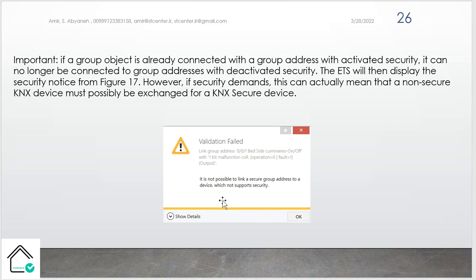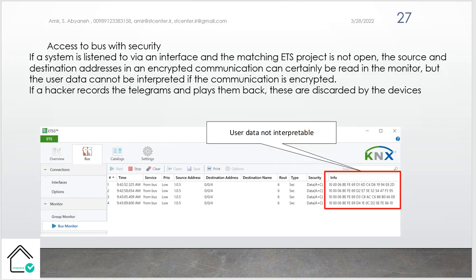If your group address is in automatic mode and you want to add a group object, it asks you, it's automatic, and if you add the non-secure group objects, it automatically turns to non-secure group addresses. But if your group address is secure and is in on mode, and you want to add the non-secure group addresses, it provides you the warning that you cannot add it anymore. Okay, good.